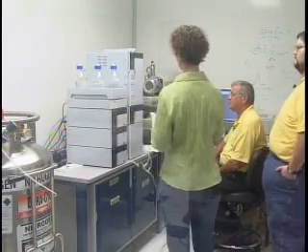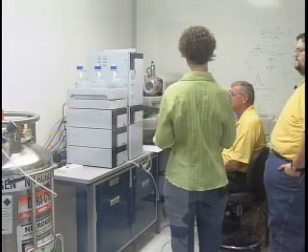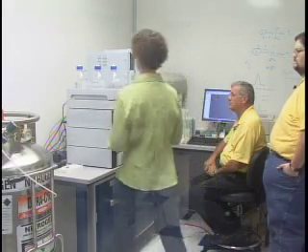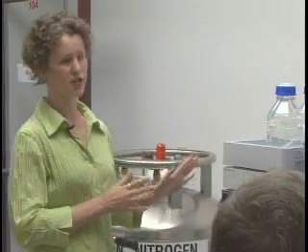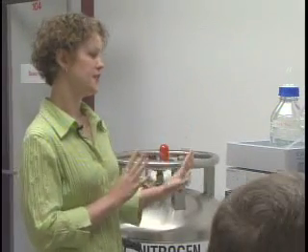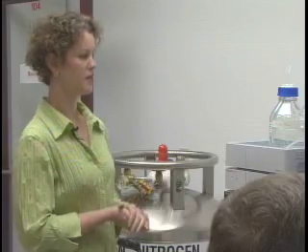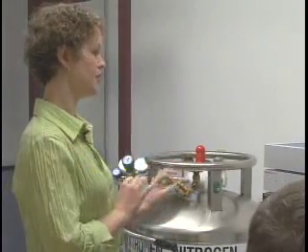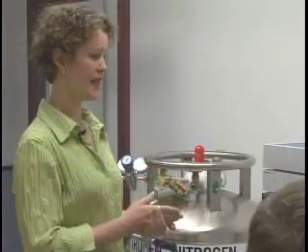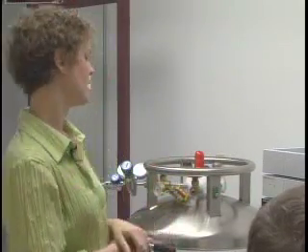The organic mobile phase is ammonium formate and formic acid in a methanol solution. We've also got a syringe wash for the autosampler section, which is a 50/50 of both the aqueous and the organic mobile phase. Standard references: the aqueous is usually an 'A' designation and the organic mobile phase is usually a 'B' designation.